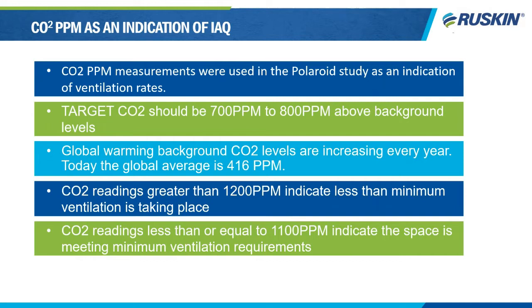So during this pandemic, the difference between background measurements and indoor space measurements needs to be reduced, and that means your CO2 parts per million set points should be reduced to bring in more outside air. So if you have CO2 readings in the space that are less than 1,000 parts per million, this would indicate that the space is being ventilated correctly. If you have a CO2 sensor and it's reading around 400 parts per million, then you're standing outside. That's what our background levels are today.